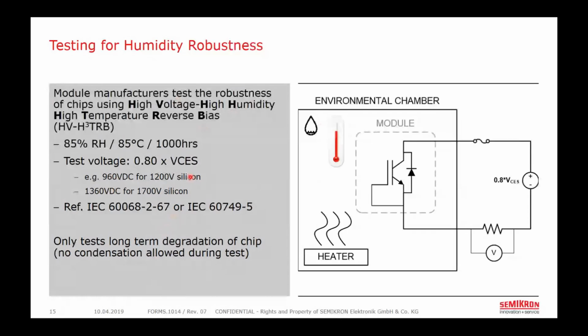an HV-H3TRB test. The chips are smaller and have different termination structures perhaps around the edge, so they might respond differently or better even, to be honest. But we would subject them to the same type of test, whether it's silicon or silicon carbide chips. Okay, so it's about the packaging and not the chip necessarily. It is about the chip. The chip design plays a role in its robustness, of course, but we don't test it any differently. We want to hold it to the same standards, because this is intended to represent the worst case environment.